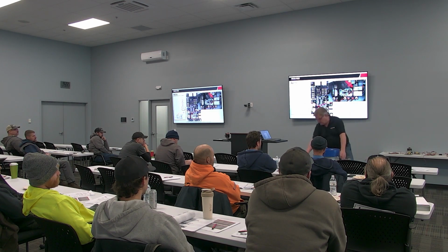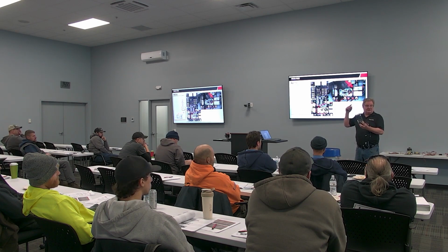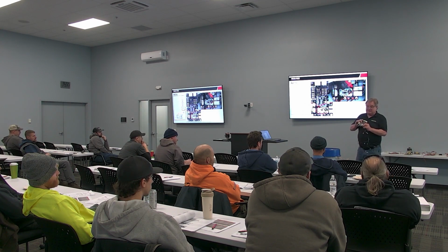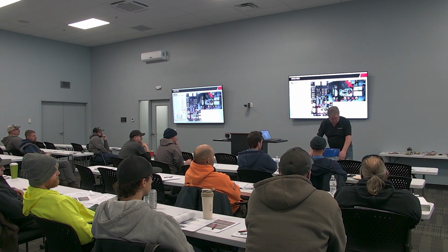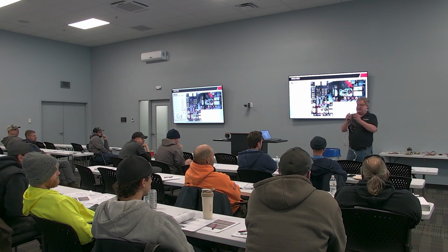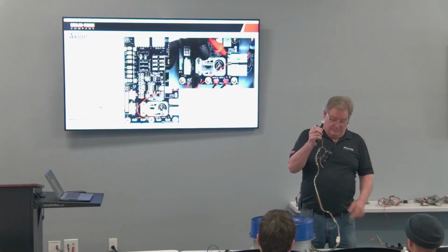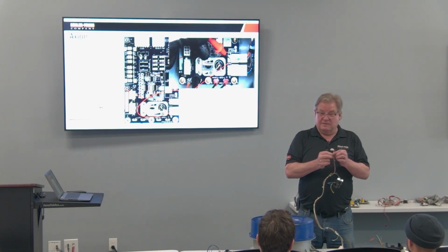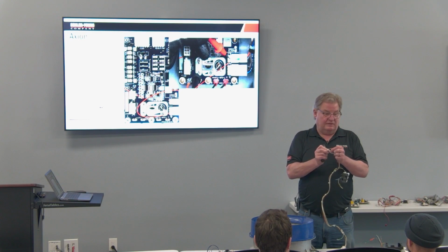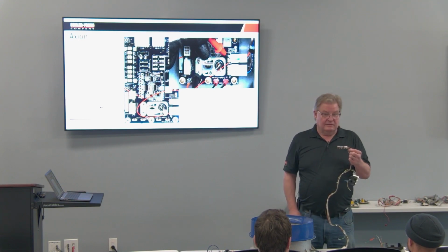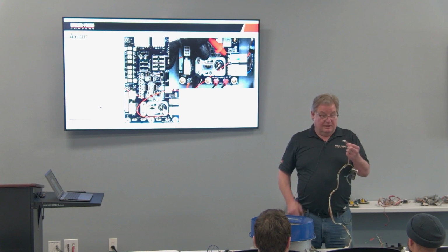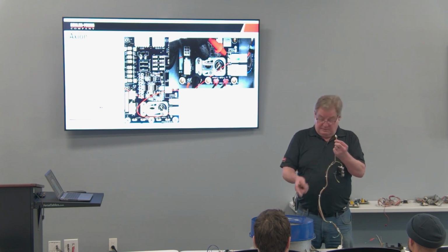I adjusted it, and when we set it up, I took it from 10 and set it to 9, because that's going to affect the blower speed. So on a call for this blower, it's going to send that 9 volts back down this gray wire, and the motor should come on. In theory, if I were to jump the orange and gray together, I'm sending 10 volts DC to that motor, and the motor should come on. Right? I could put a jumper right there, and that motor should run up to full speed.